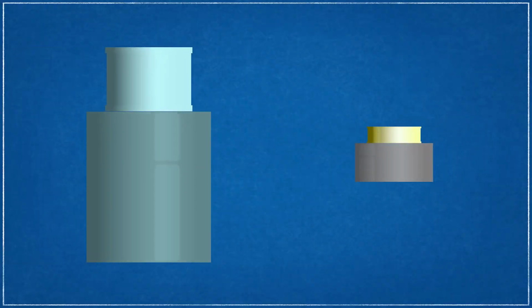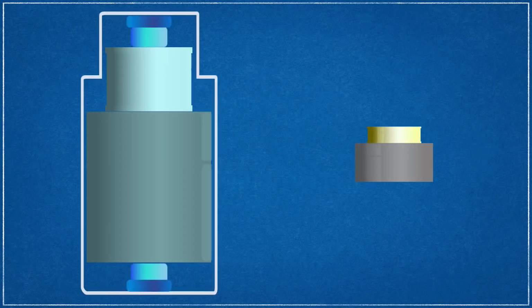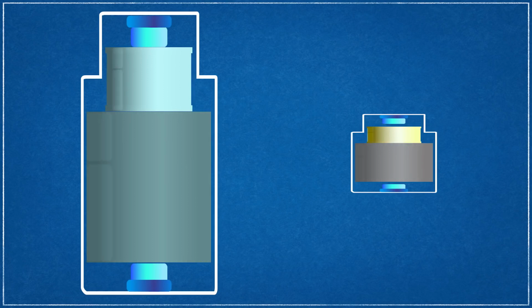Flywheel energy storage system designs generally fall under one of two strategies: low-speed flywheel systems that operate under 10,000 RPM and high-speed variants that can approach 100,000 RPM. Low-speed flywheels are usually made of heavier, metallic materials and are supported by either mechanical or even non-contact magnetic bearings that support the load with magnetic levitation. High-speed flywheels typically use lighter, stronger composite materials and require magnetic bearings. Because flywheel energy storage systems usually enclose the flywheel within a vacuum to reduce friction, the primary point of energy loss happens at the bearings that support the flywheel.